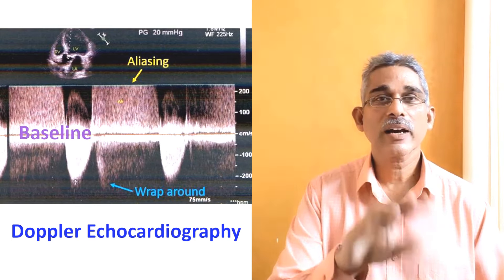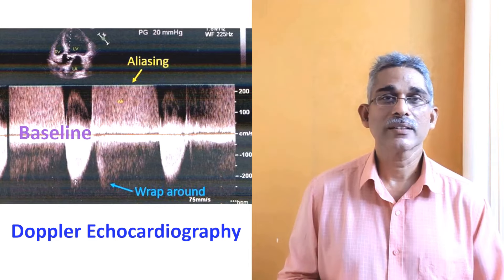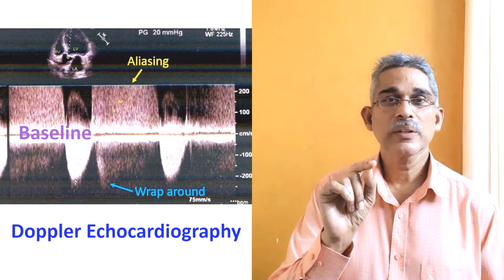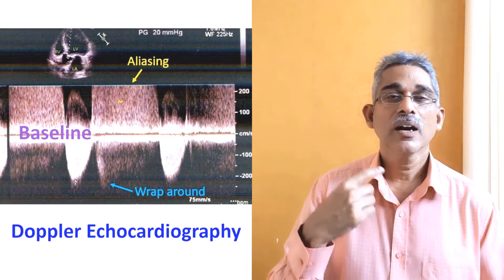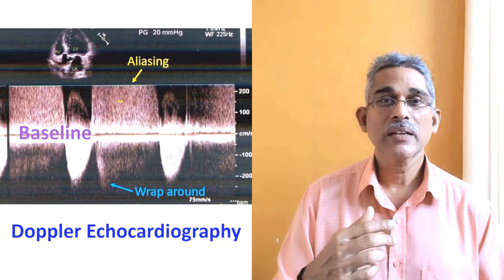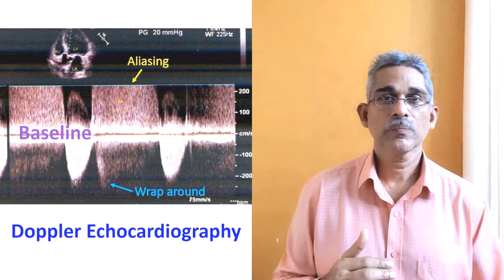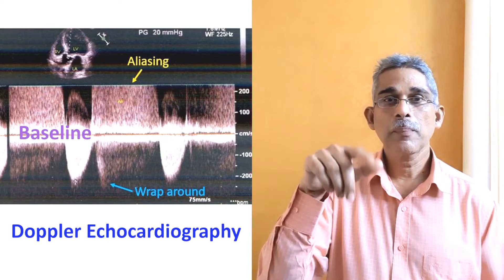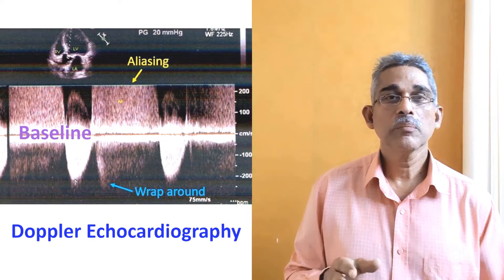When the reflected signals are received, the change in frequency tells you whether the blood cells are moving towards or away from the transducer. Suppose you are sending out 2 MHz and there is a slight change in the received frequency — whether increasing or decreasing indicates the direction of blood flow. In conventional Doppler, the signal was depicted as a graph above and below the baseline.